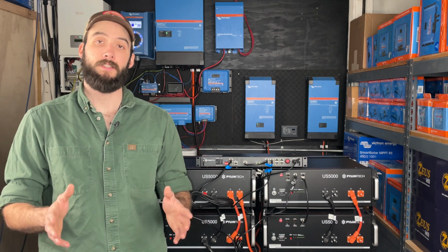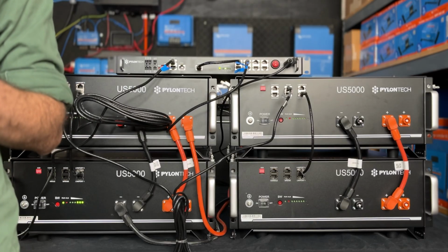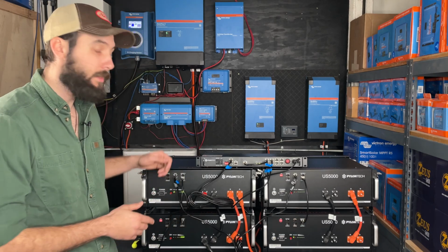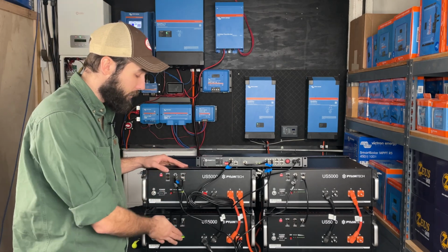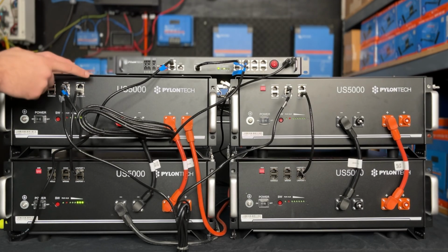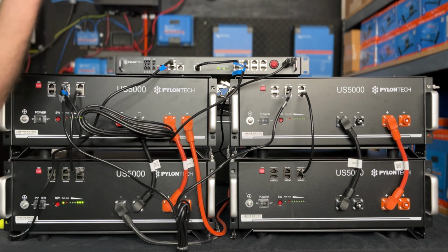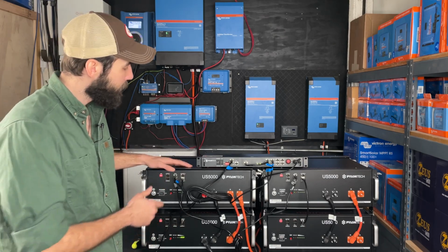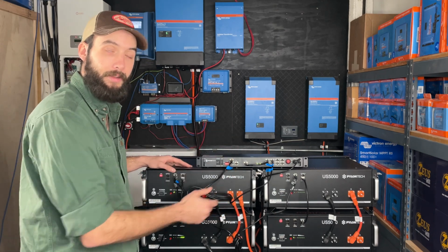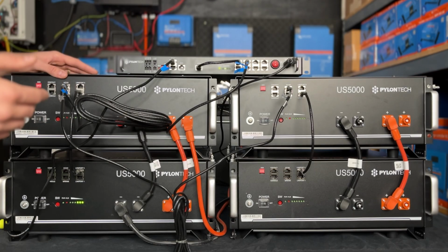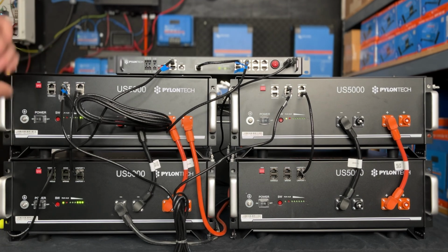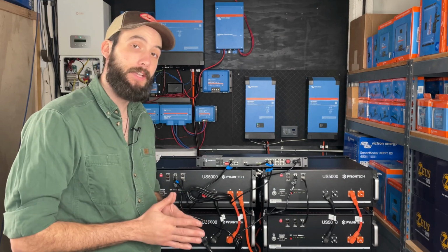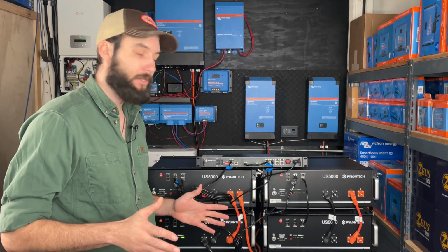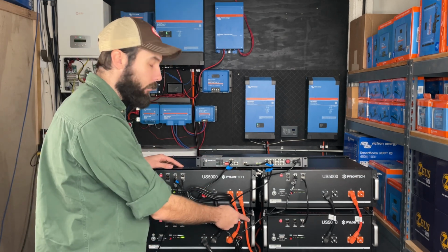The second reason is to take advantage of the advanced capabilities of the BMS. Every battery has a battery management system in it, and the BMS in the master battery acts as a systems-level manager for every battery underneath it. This BMS is actively monitoring every battery, checking its status, its throughput, what power it can actively give and receive at this moment, and compensating for any inefficiencies caused by different wire lengths.